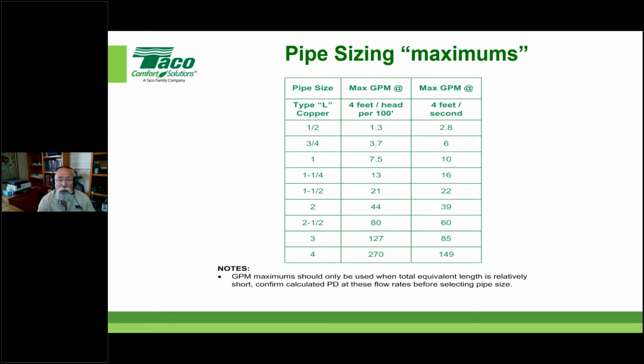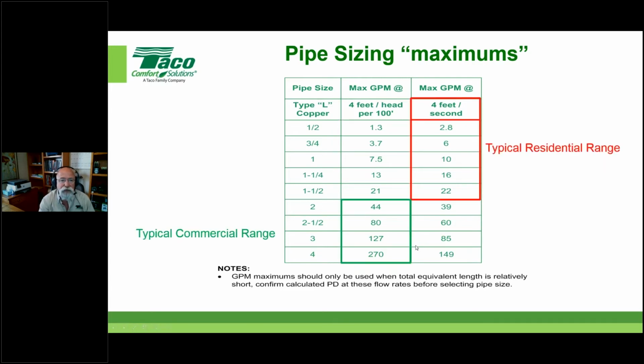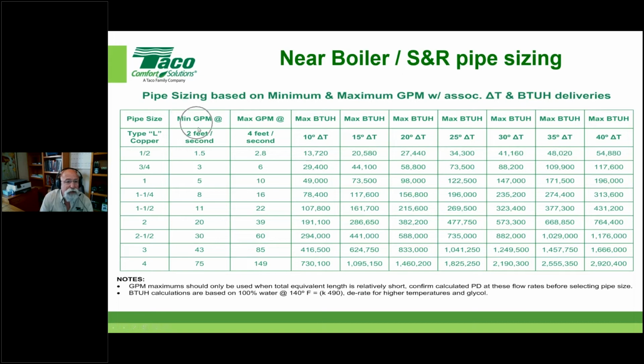There you go. If you want to go back and look at it, when we talk about this right here, if you keep those secondary headers in and around 2 feet per second, that's kind of a heads up that keeps them nice and copiously sized. So there you go, use your 2 feet per second on that close near boiler piping header for multiple zones, and then use 4 feet per second for your maximum velocity out on those secondary pipes or anything. Generally speaking, these would be your maximums.